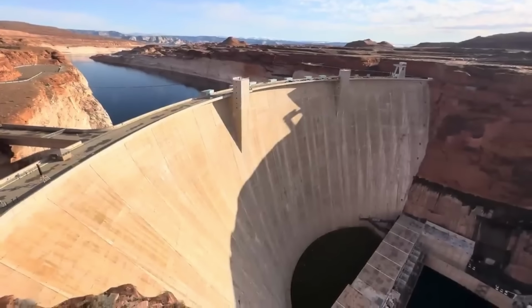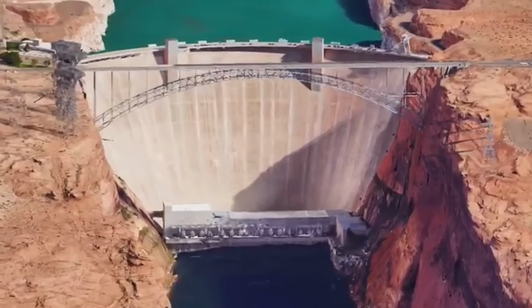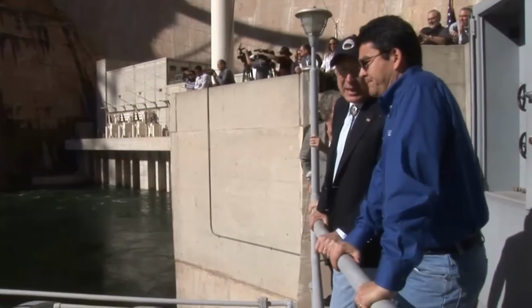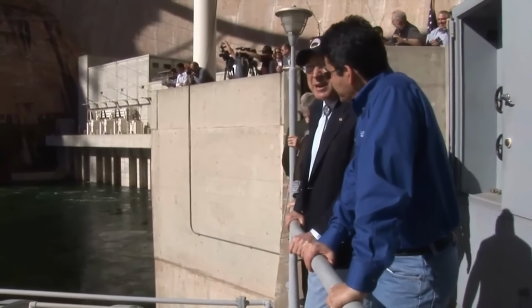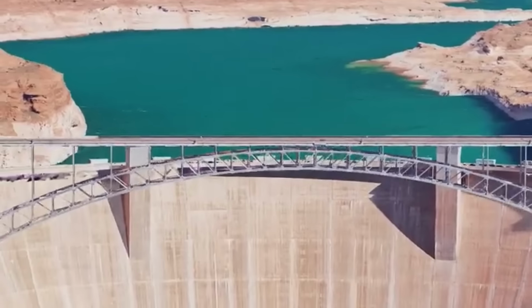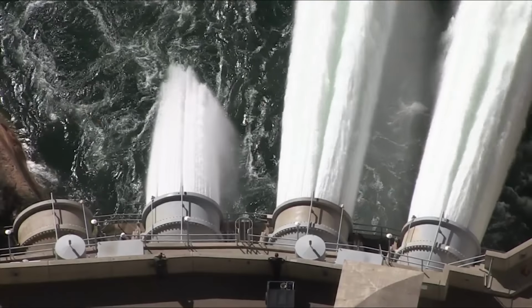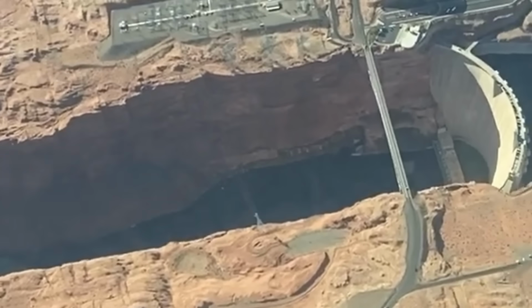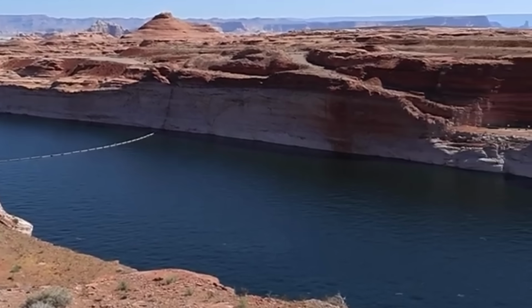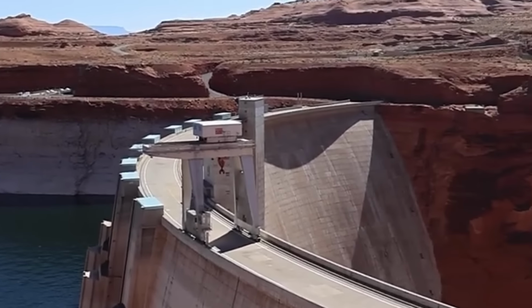There are 2 versions of Glen Canyon Dam, and both are true at the same time. Version 1, a fully intact concrete arch, generating power, releasing water, no structural failure. The Bureau has stated the dam faces no structural risk. The pipes were relined, operations continue. Version 2, the same dam roughly 37 feet above the shutdown threshold, with backup pipes that were never designed for sustained use, a second gap below 3,370 feet that has no funded solution, and an agency studying infrastructure modifications on a timeline that ends years after the crisis window opens.